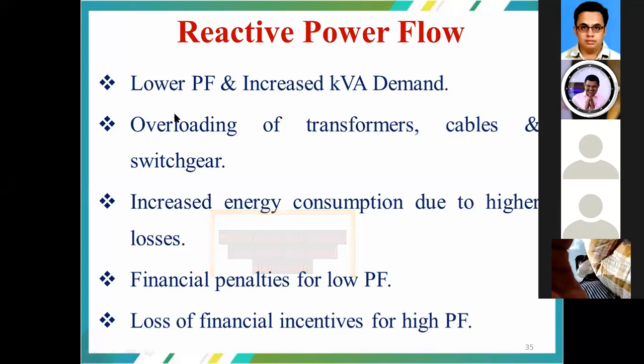And the next one is the reactive power flow, and we are all aware of that. Whenever we go for power electronic converters or power electronic switches, the requirement for reactive power is going to be higher, which in turn is going to decrease the power factor. We know that the power factor is defined as the ratio of real power to apparent power. So if the kVA demand increases, you are going to have a lower or reduced power factor. And this reactive power flow is going to overload the transformers, cables and the switchgears.